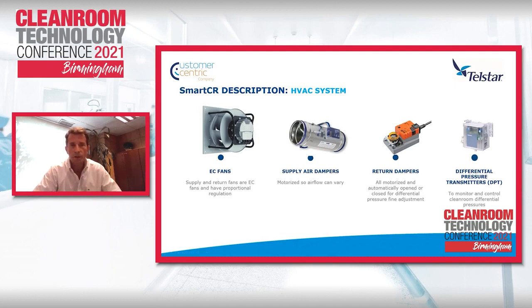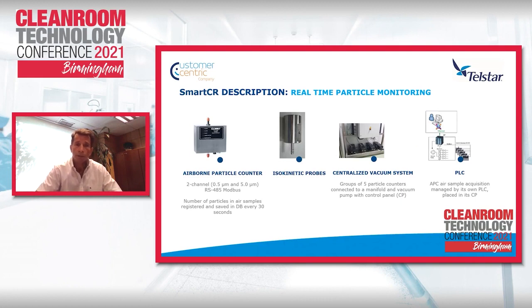Mechanically, the system is everything conventional. I mean, we will count on the same EC fans in the air handling units. We will have motorized dampers in the supply. We will have the typical, conventional motorized return dampers, and obviously the differential pressure transmitters. We will have the particle counters, as many as the risk assessment determines, with their isokinetic probes, their centralized vacuum, and the dedicated PLC.